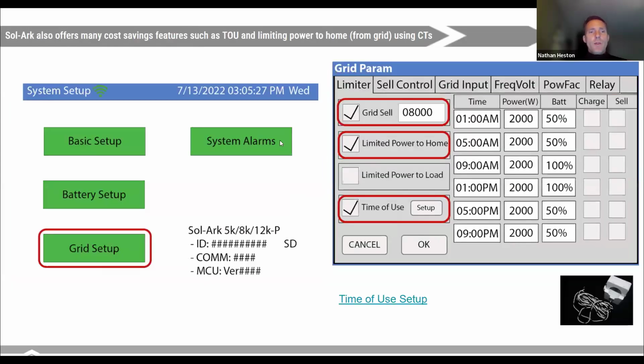We do have the ability with the Sol-Ark 15k, when we're doing whole home backup, to do different things. One of the things we can do is export excess solar back to the grid. We can limit how much excess solar we're selling back to the grid. So if you have a limited agreement with your utility provider, or if you're sending back through a partial backup system and through a main load panel and you don't want to go over the 120% rule, which would specify 20 amps back on a 100 amp panel, or 40 amps back on a 200 amp panel, you can set that value here.